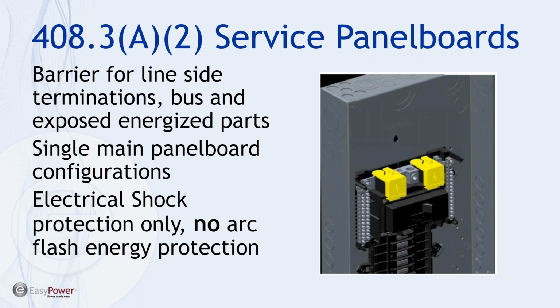So in EasyPower, we have a reference or a control that excludes the main breaker in the panel, and it's really a function not so much of whether the breaker can do its job. It's more a function of the size of the plasma ball and potentially whether or not it can engulf the main breaker, which would allow the arc to jump the breaker and effectively negate the potential protective values of the breaker itself. So let me jump into EasyPower.